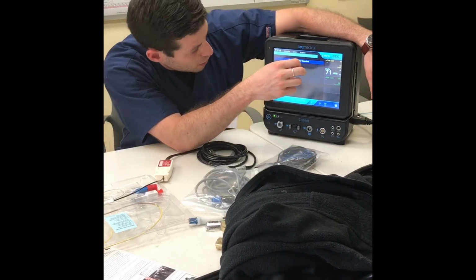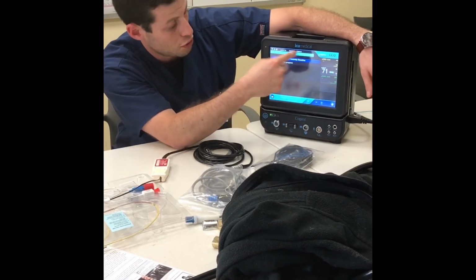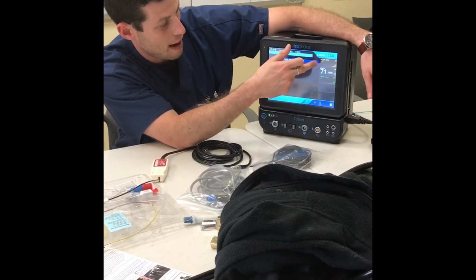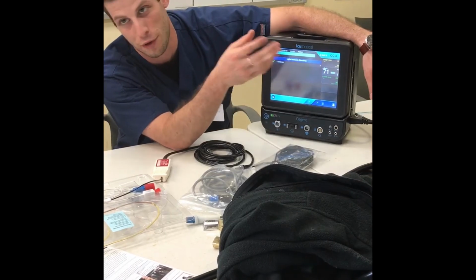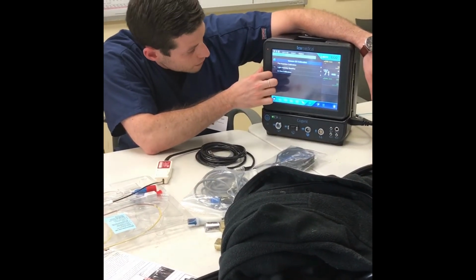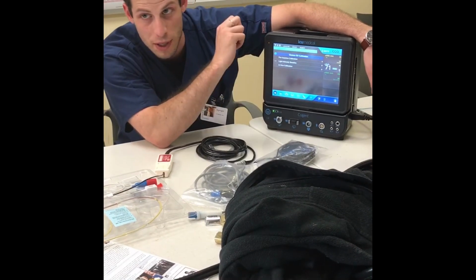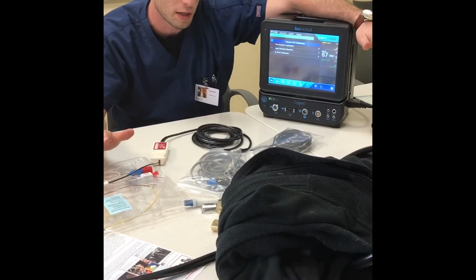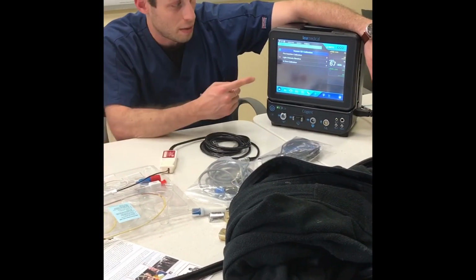So what it's doing now is, just so you saw, if you were watching, everything I do when I hit the green check is your confirm. That's your enter on the monitor. And then continue. And then our number shows up. All right, so you just calibrated the catheter before you stuck it in the patient. You did your light intensity baseline, it passed. Now that number you're looking at is exactly what the SVO2 is.